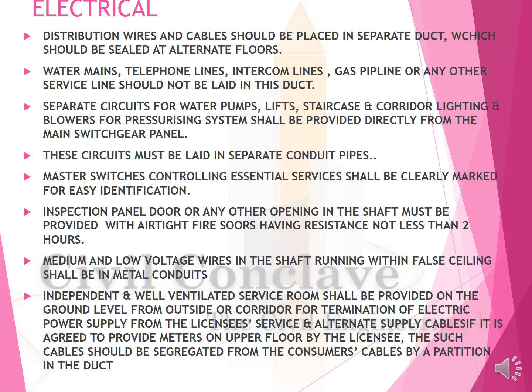Electrical. Distribution wires and cables should be placed in a separate duct, which should be sealed at alternate floors. Water main, telephone lines, gas pipeline, etc. should not be laid in this duct. Separate circuits for water pumps, lifts, staircase shall be provided directly from the main switchgear panel. The circuits must be laid in separate conduit pipes. Master switches controlling essential services shall be clearly marked for easy identification.